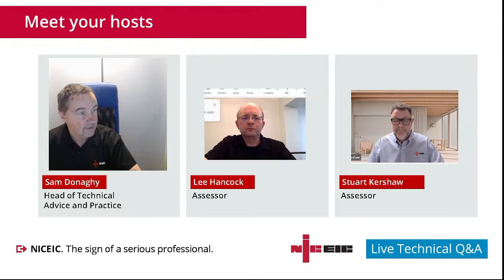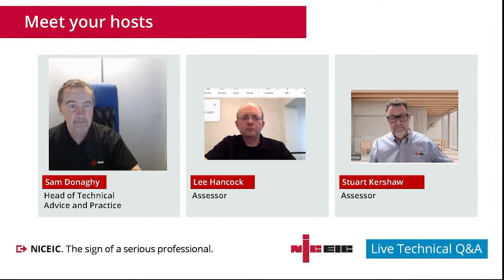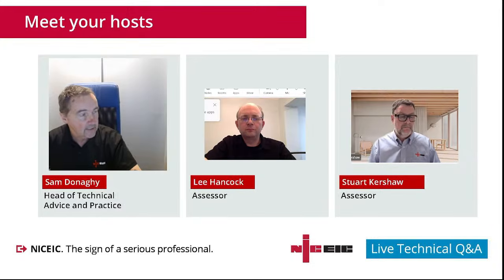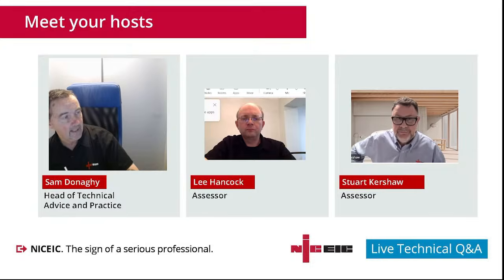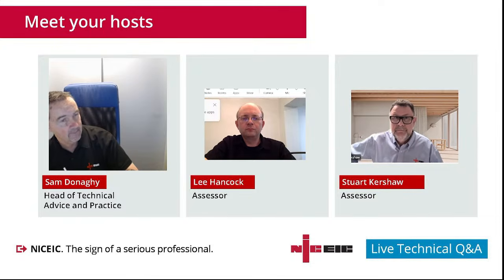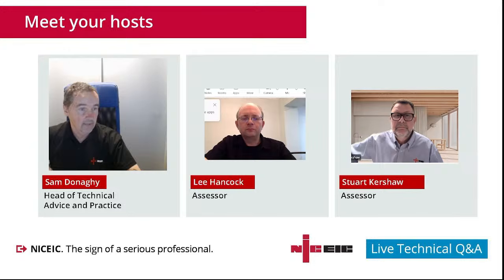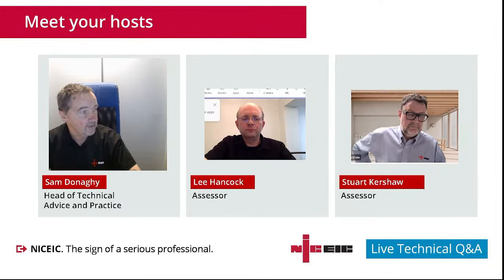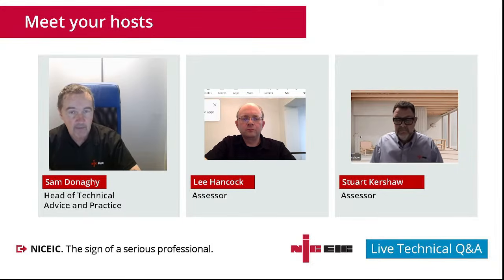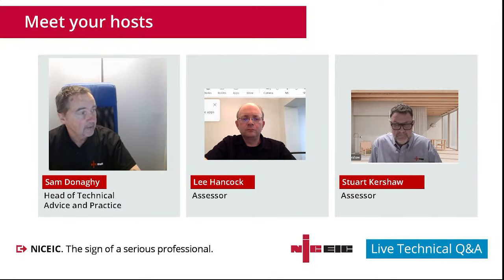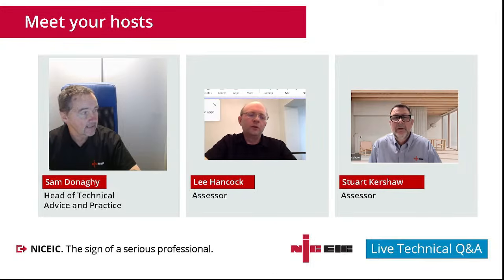You're not stating that you're the 62305 lightning protection system designer. You're stating that you're the designer of the electrical installation. So if it's not readily available from the lightning protection system engineer, another alternative might be from your chosen SPD manufacturer. That would help you with IMAX values and the rating of the overcurrent protective device if it's separate from the SPD itself. Would you guys add anything else to that?